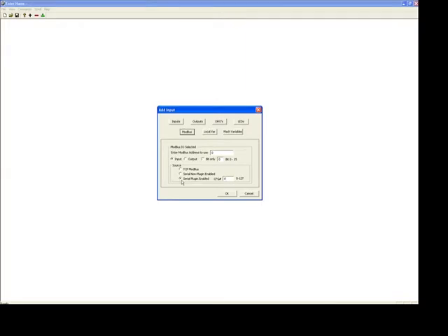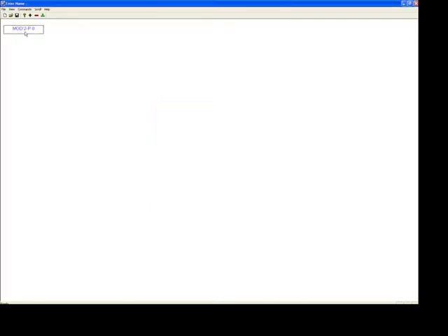And you can see that when you select serial plug-in enabled, not only do we set a Modbus address up here, and that number would be 0 to 127 for the data within that configuration group, but you set a configuration number. So by telling it that I want, say, address 2 from serial plug-in enabled configuration 0, we would get Modbus address 2 plug-in enabled, and it is currently in configuration 0, and that's what this mod2p0 means. Modbus address 2 plug-in enabled configuration 0.